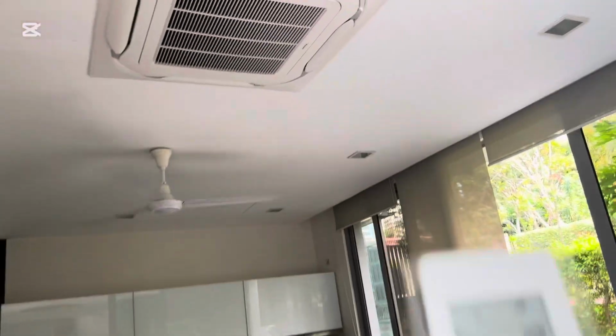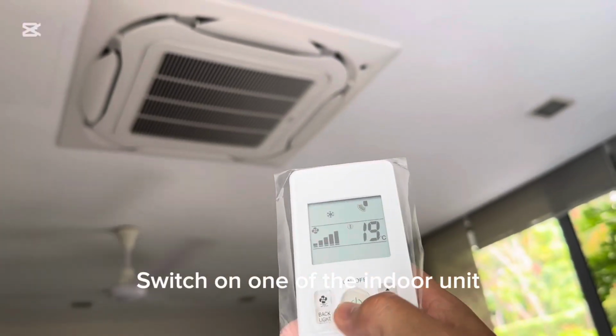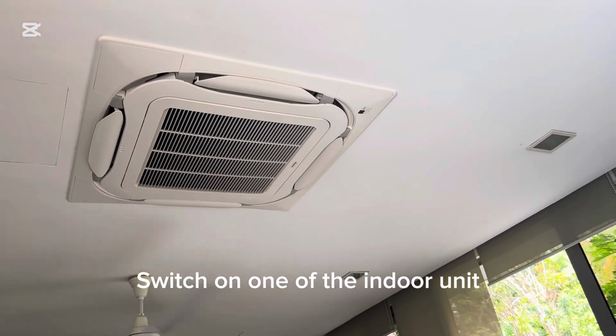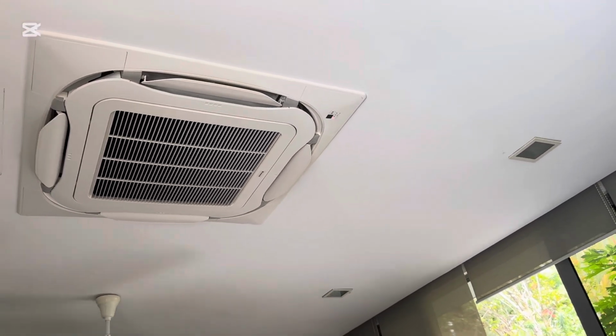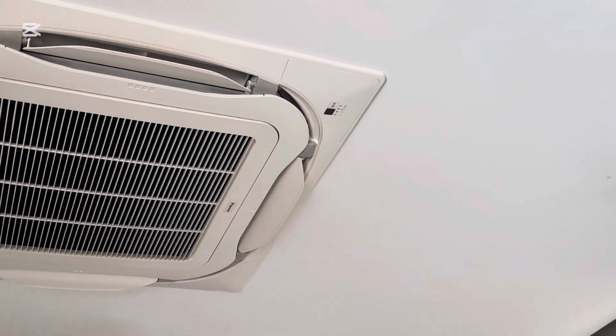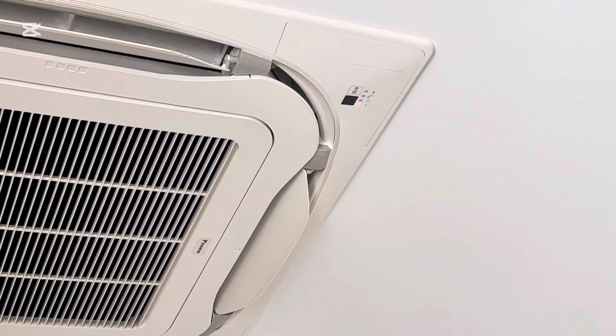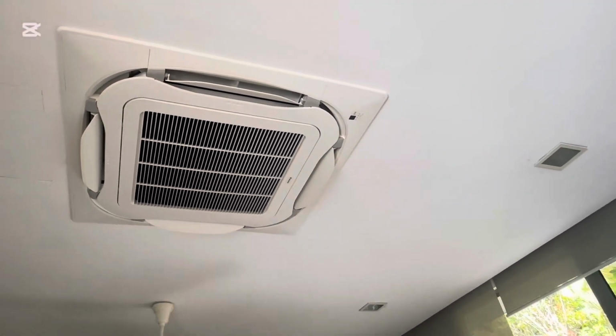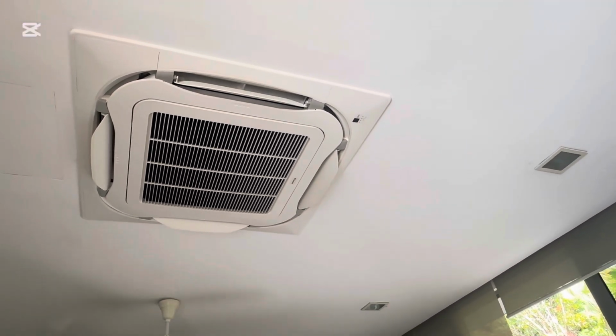F4-02 and F4-04. Okay, after we use the checker to check, we found one of the indoor unit LEV valves is unable to fully close. Okay, we go take a look at the indoor unit. We switch on one of the indoor units. The indoor unit is blinking, but the outdoor is working actually.